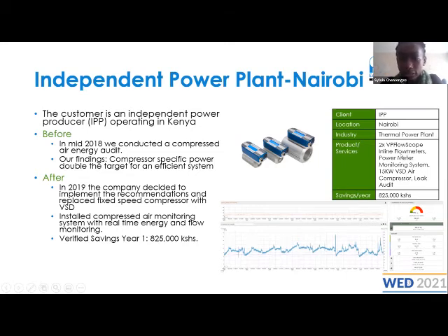And then we installed a power meter, an inline flow meter, and a monitoring system from CAMS. From the monitoring system, we can look at the key parameters, that is the pressure and the flow rate within the system, and then how much power they are consuming and whether they are operating efficiently. They were able to save around 800,000 shillings within a year of operation with the changes that we incorporated. So with that, thank you for listening to my presentation.